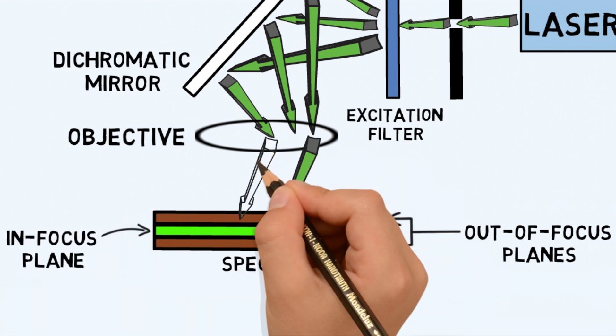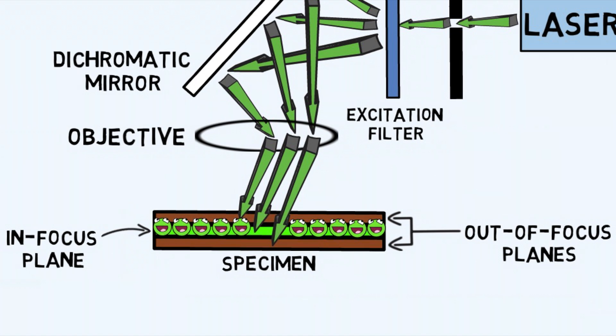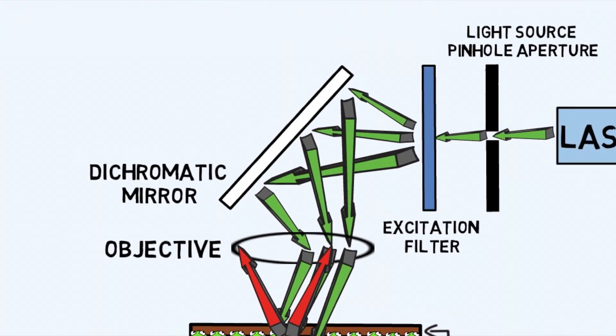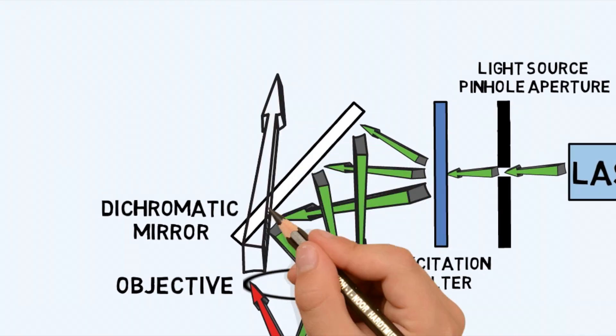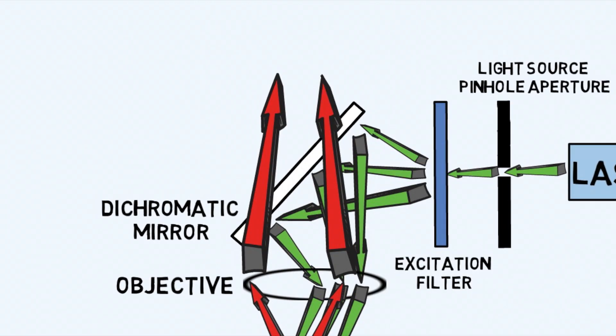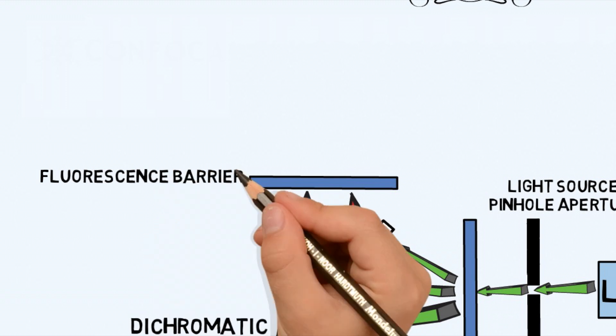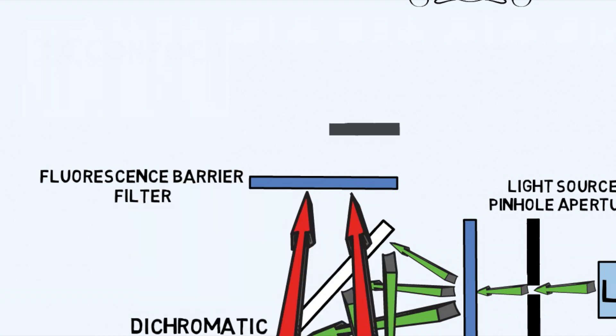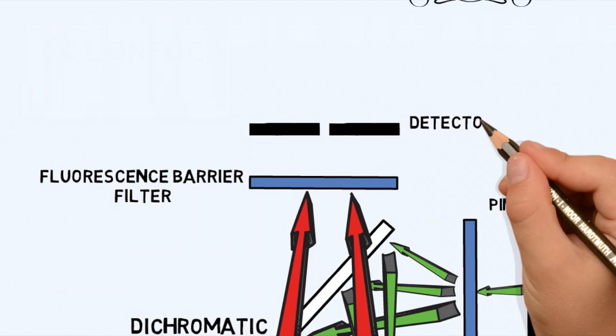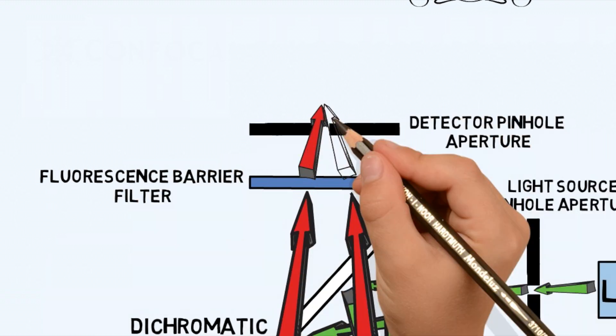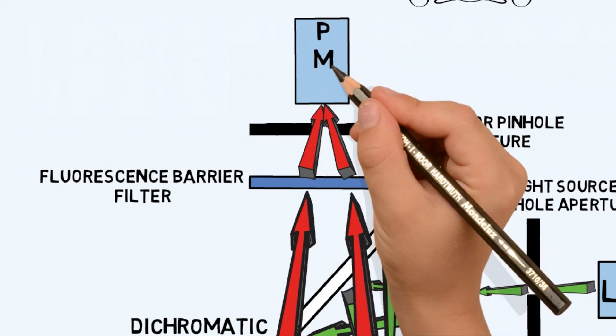Fluorophores in the specimen get excited by the light, causing them to emit detectable fluorescence. The fluorescence emitted from the specimen has a long wavelength that then passes through the dichromatic mirror fluorescence barrier filter and is focused into a second pinhole aperture into the photomultiplier tube.